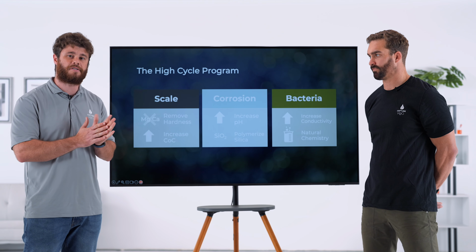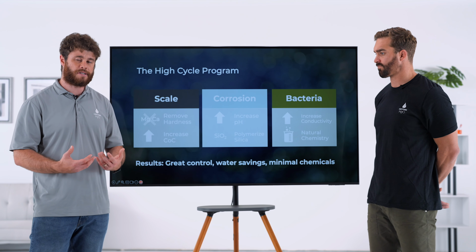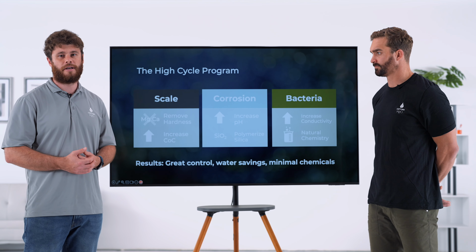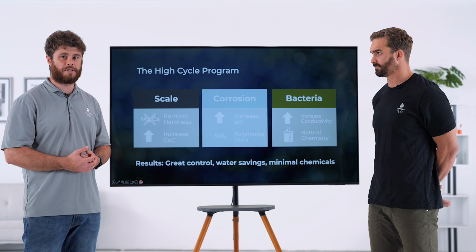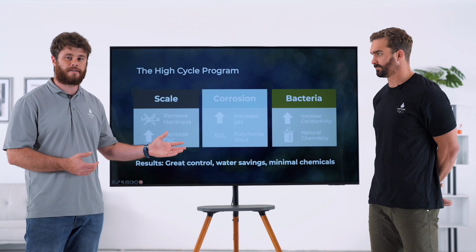There are bacteria that can exist in that high pH environment, and there is also bacteria that can exist in a high conductivity environment. However, together, in a high pH and high conductivity environment, there is no bacteria on Earth that can exist in those conditions. And that's what we're creating naturally with the high cycle program. Installing water softeners on the makeup line to remove all of the hardness gives us the ability to increase cycles, increase pH, and increase conductivity in the cooling tower to control for corrosion and bacteria.